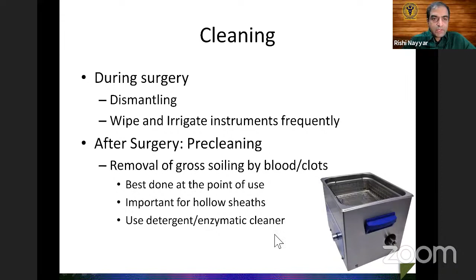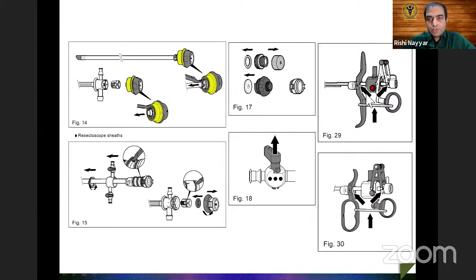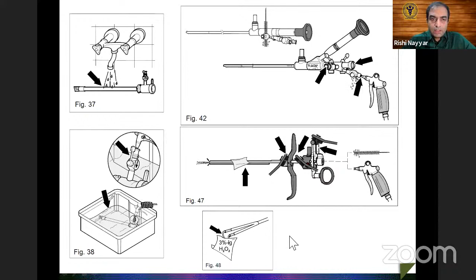And after the surgery, the same process has to be repeated. We can use enzymatic or ultrasonic cleaners also, but what is important is that we should dismantle each and every part of the resectoscope, the individual sheaths, the Luer locks, and each nook and corner of these working handles. All these should be properly cleaned with the brushes or the pressurized water or air. And only after proper cleaning and drying, then the sterilization has to be done.